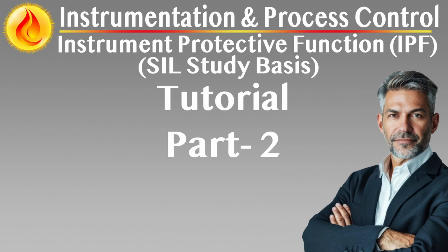Design margin and verification. For the IPF to be considered effective, the total IPF response time must be well within the PST, allowing for margin and tolerances. SIL verification must document that all components from sensor to final element perform within the required time. Design margin, typically 20 to 50%, is recommended to accommodate degradation, variability, or startup conditions.